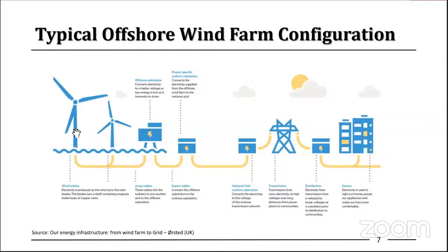Typically it uses 33 kilovolt or 66 kilovolt AC connections to connect to the offshore substation, where it steps up to the transmission voltage - this could be HVAC or HVDC. Typically the export voltage is decided by the voltage level at the point of connection. For the UK this is 400 kilovolts AC, and in the US market it's about 230 and so on. In AC connected offshore wind farms, sometimes a midpoint reactive power compensation substation is used when the distance to shore is much larger, more than 100 kilometers of offshore cable.